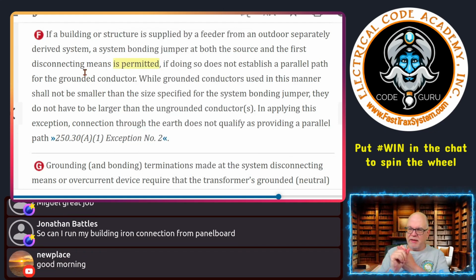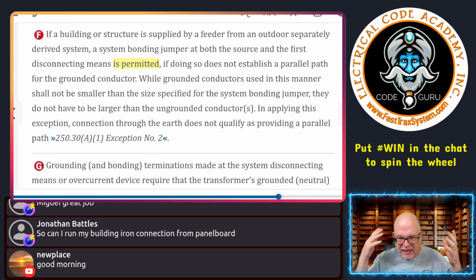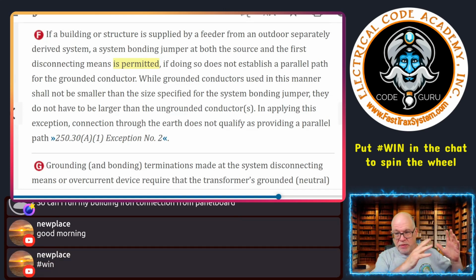All right, so it's a permissive, right? If it's outdoor and indoor, typically we might see something outdoor and you're thinking that's remote, right? And you put a system bonding jumper there. Now I come to the panel that's inside. Can I put a system bonding jumper in there? Remember what I said other times, it's discouraged? But again, here's the example of where it would be permitted to do both, but you've got to meet these caveats. And what are they?